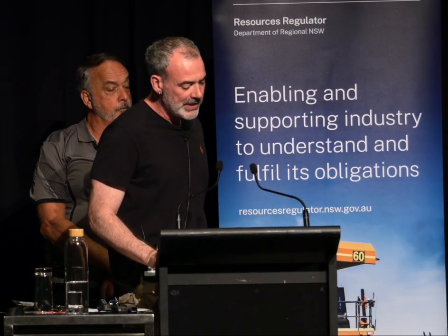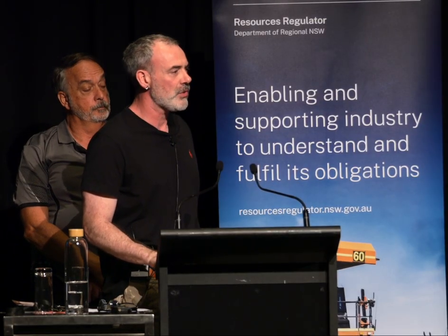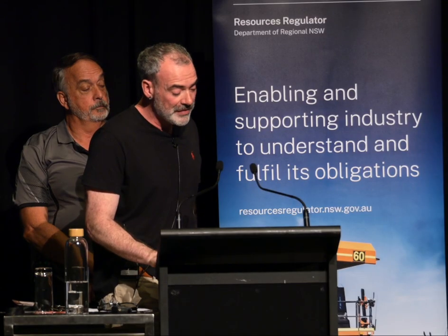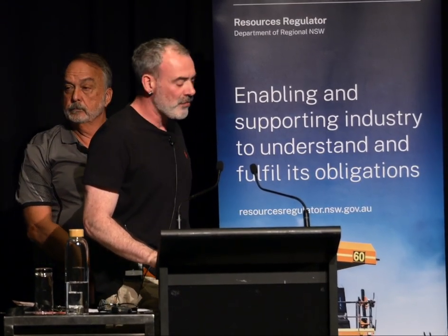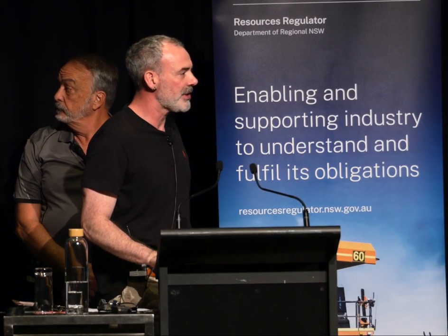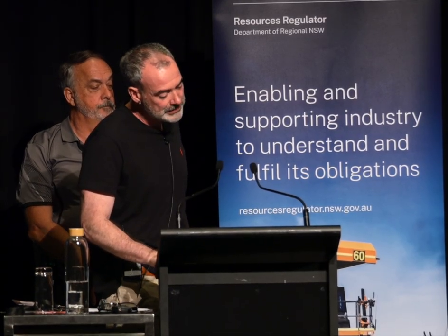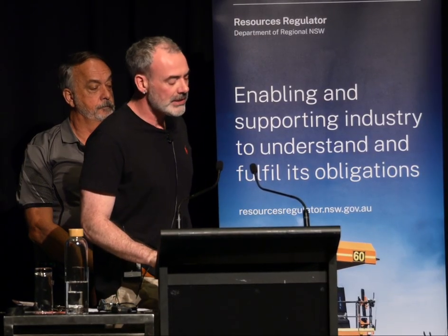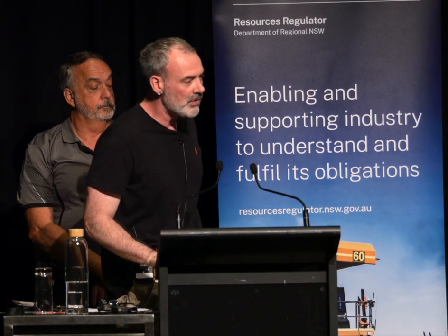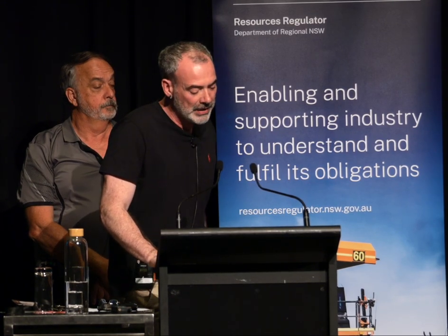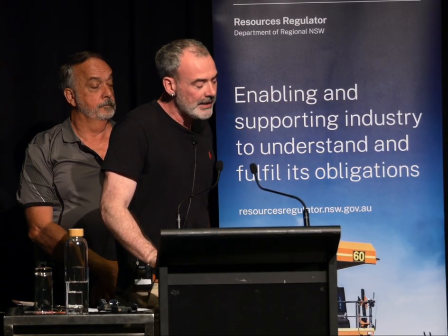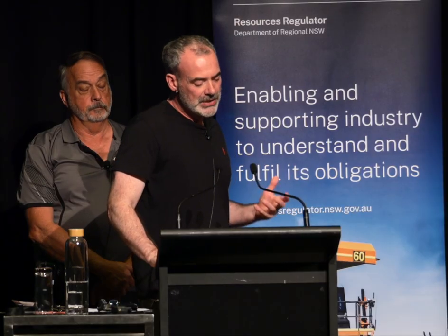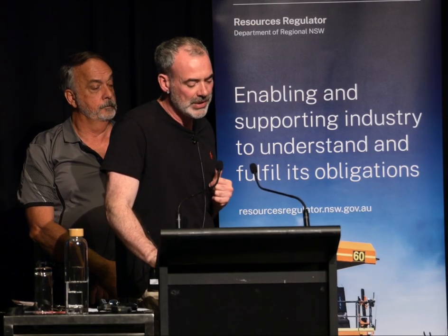Okay. So continuing on the theme of water, now talking about life extension. During operation, water levels can increase due to defective silica gel breathers, defective seals, and also degradation of the paper produces water. In mineral oil-filled transformers, a consequence of increasing water levels can be a reduction in the breakdown voltage to levels that are deemed to be unfit for safe operation, so that affects the reliability of the transformer. Natural ester can hold 10 times more water than mineral oil. At 20 degrees Celsius, it becomes saturated at 1,000 parts per million. And this increased saturation point is why the breakdown voltage of natural ester is more robust to water, so you achieve potentially increases in reliability.